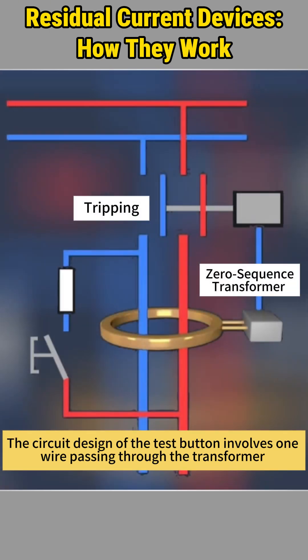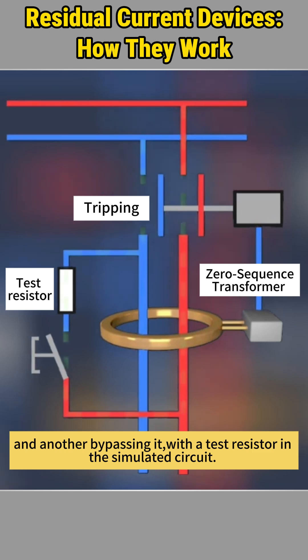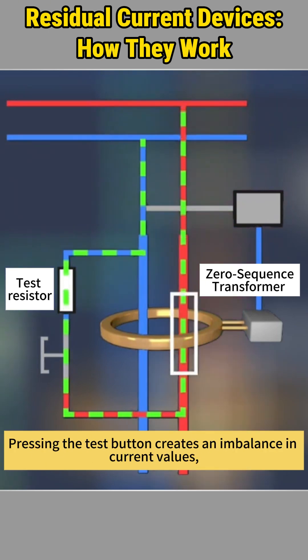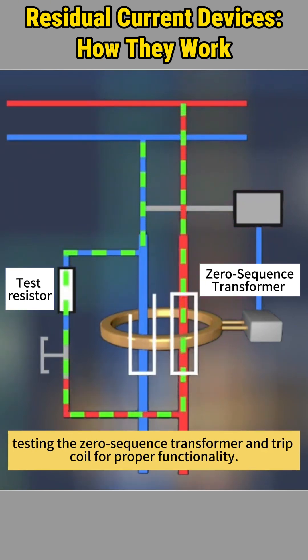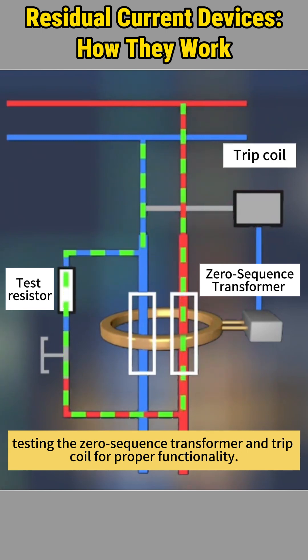The circuit design of the test button involves one wire passing through the transformer and another bypassing it, with a test resistor in the simulated circuit. Pressing the test button creates an imbalance in current values, testing the zero-sequence transformer and trip coil for proper functionality.